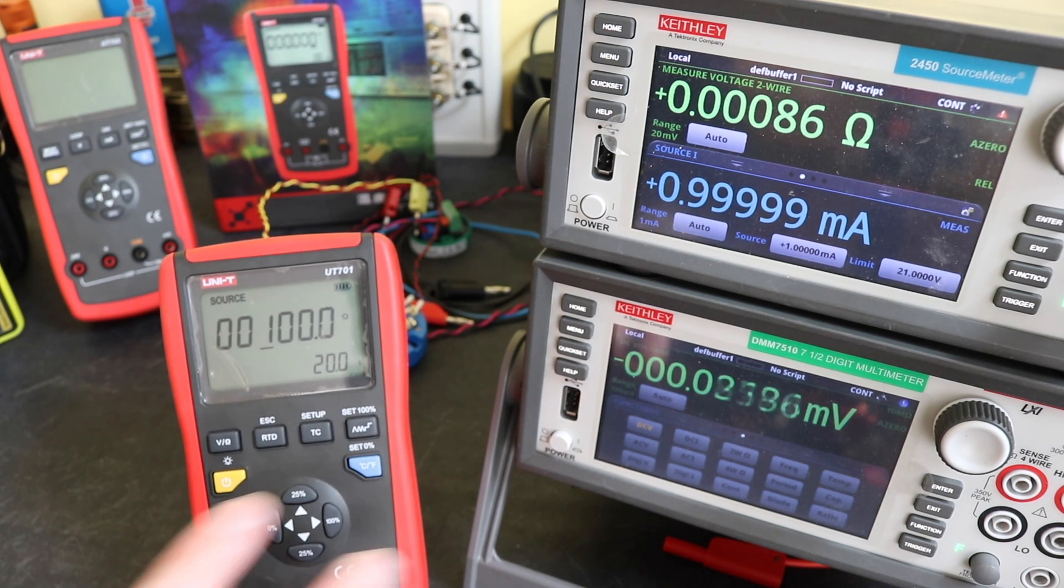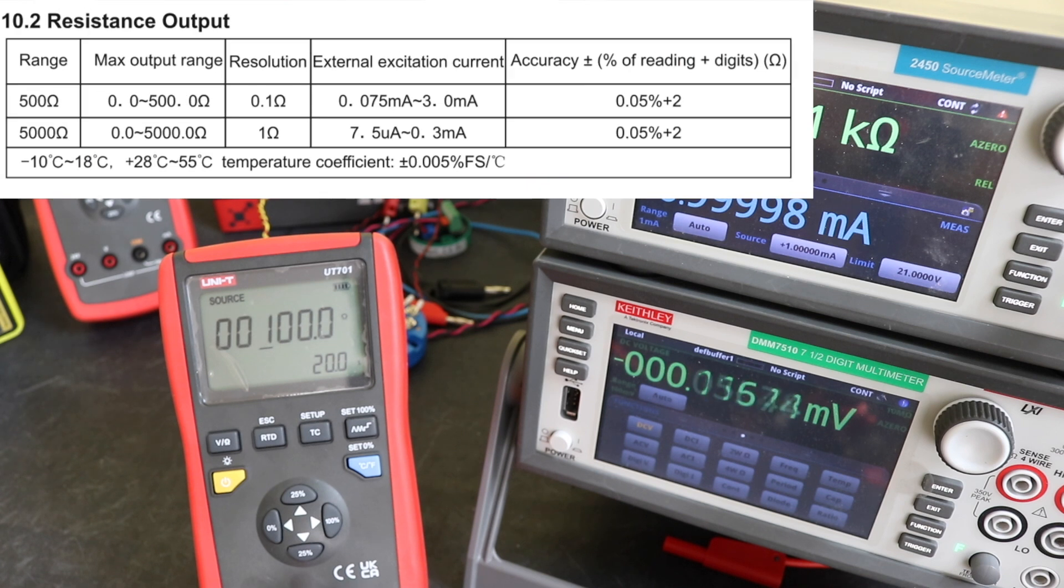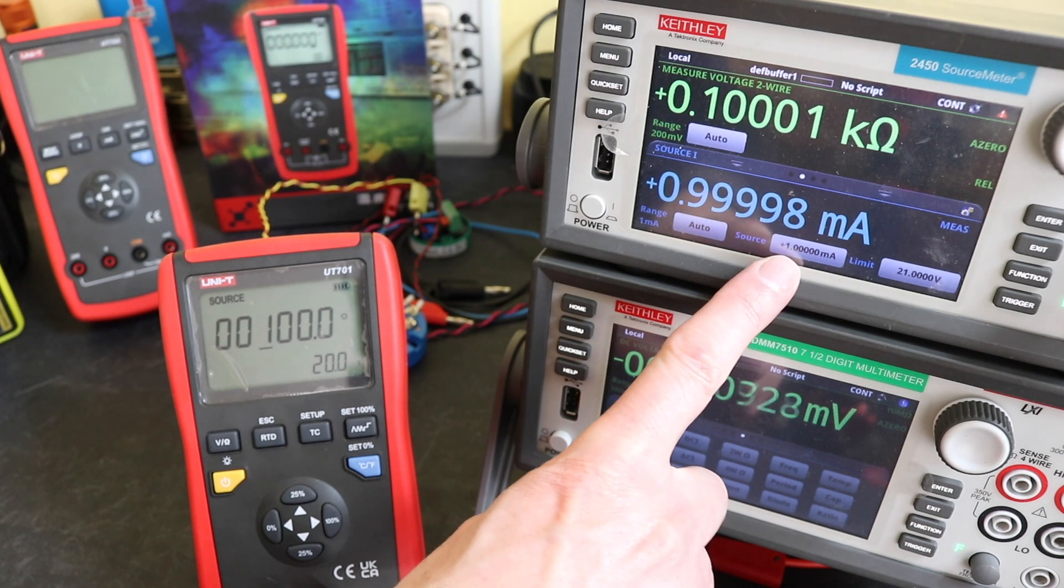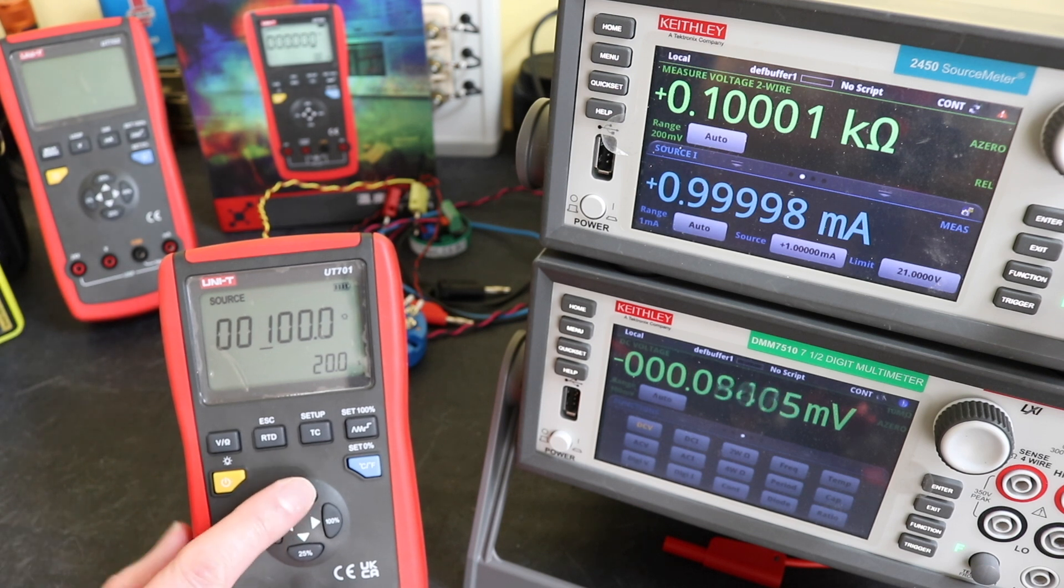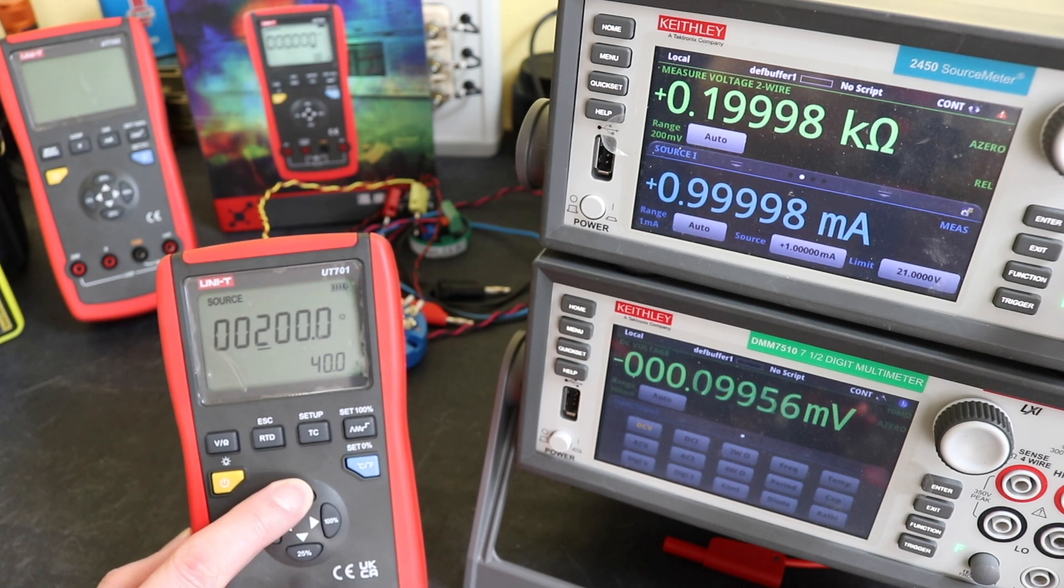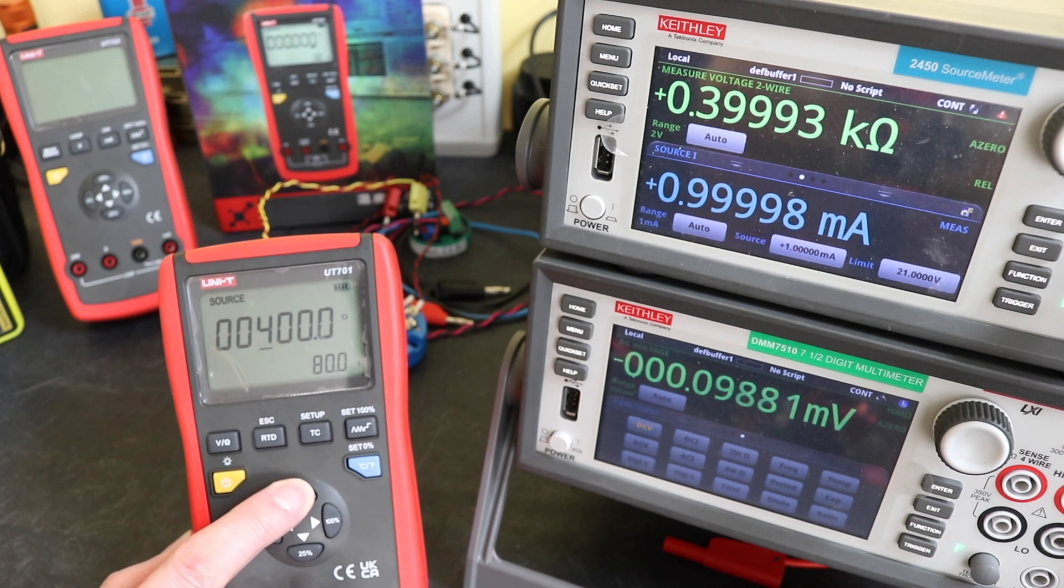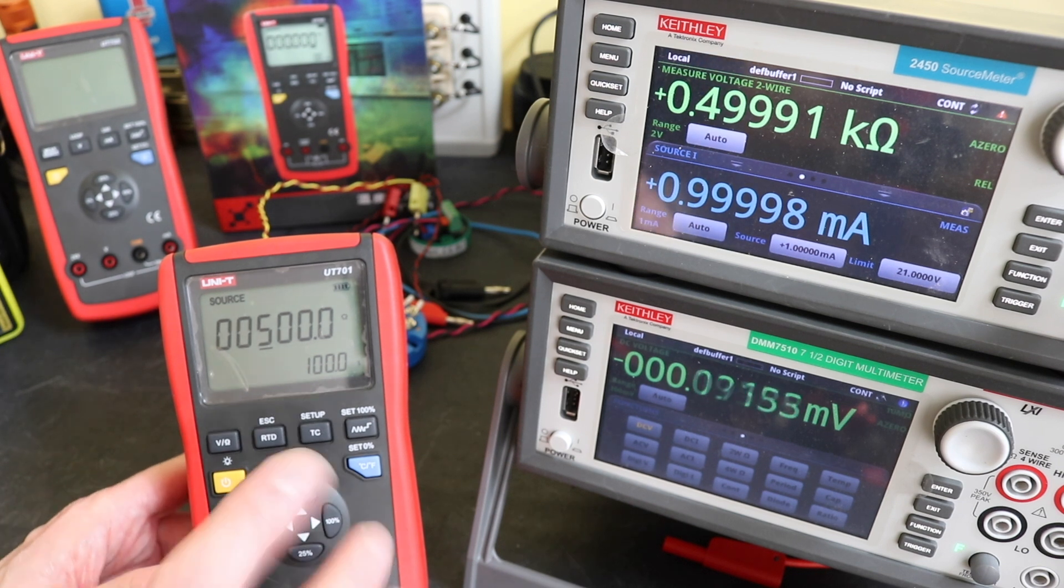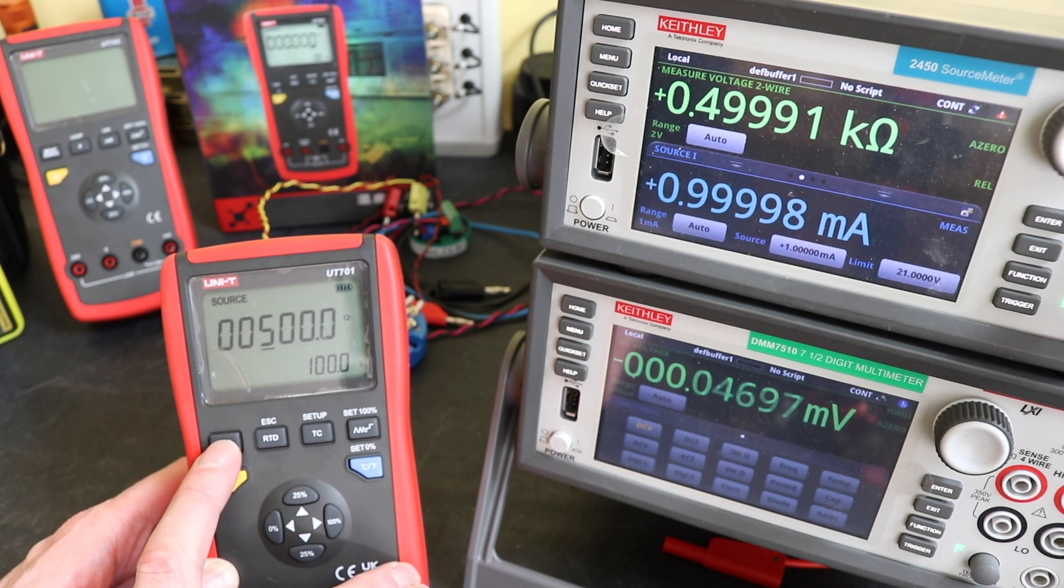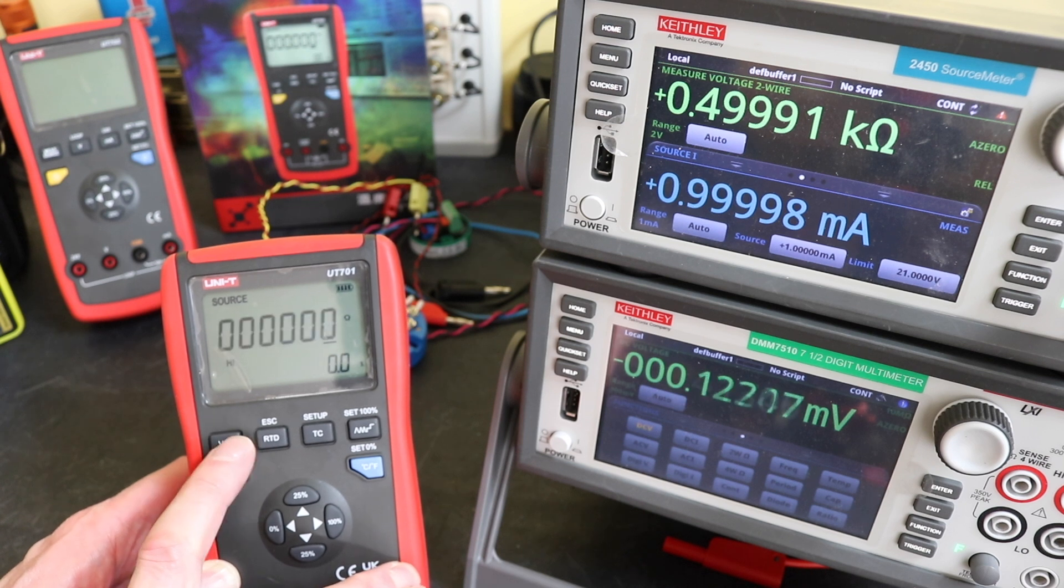Now as with some of these other units you do require an excitation current to get the resistance function to operate. You can see I've set it up to one milliamp on the 2450 source meter. You can see there we've got 100 ohms no problems. Our base range goes up to 500 if I remember correctly. Yes that's our lowest range so that can only go up to 500 ohms. We can see it's done there. We need to hit the volts ohms again to go up to our next range.